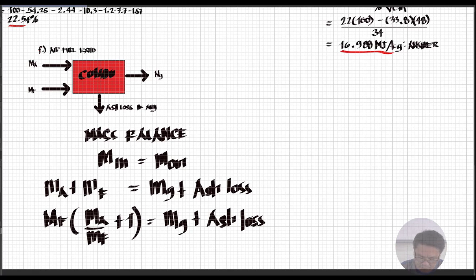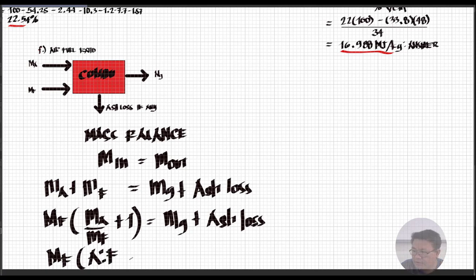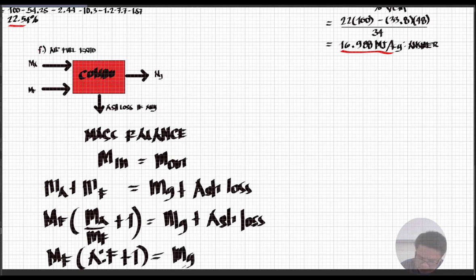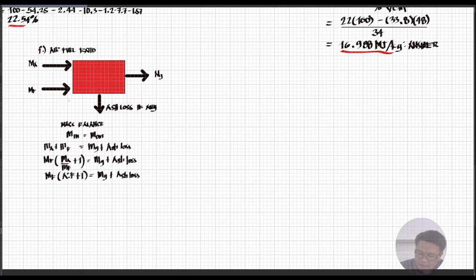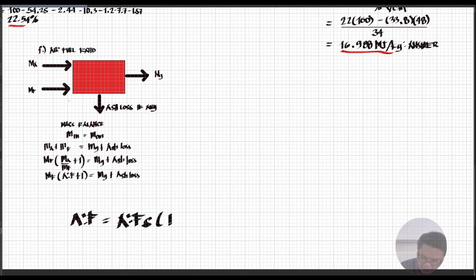This is now in the form of air-fuel ratio — the ratio of mass of air to mass of fuel. We can write: mass of fuel multiplied by the air-fuel ratio plus one equals mass of flue gas plus ash loss. The actual air-fuel ratio is equal to the stoichiometric air-fuel ratio times one plus excess air.